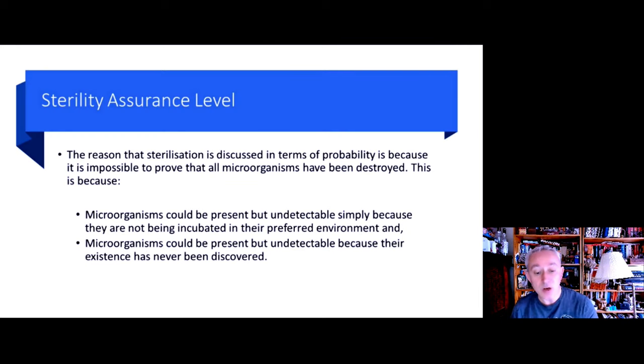Also with the sterility assurance level, the reason that sterilization is discussed in terms of probability is because it's impossible to prove that all microorganisms have been destroyed in a batch of product. This is because microorganisms could be present but undetectable. It could be that the cultural conditions that we might use to try and show sterility are not suitable for recovering those microorganisms, or it could be that the microorganisms themselves have a non-culturable aspect—they're active, they're viable, but they cannot be cultured using conventional recovery methods. This is one of the reasons why the sterility test is regarded as somewhat weak.